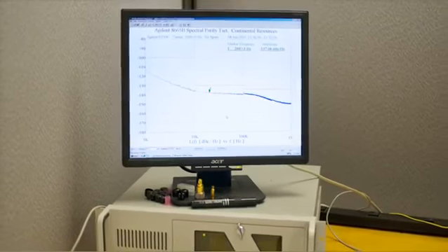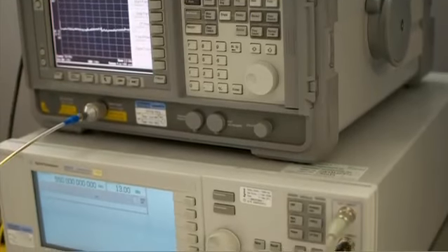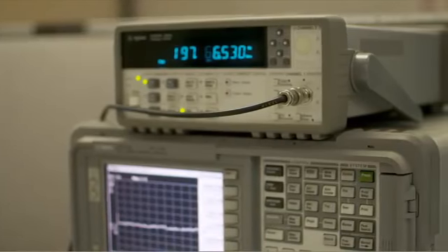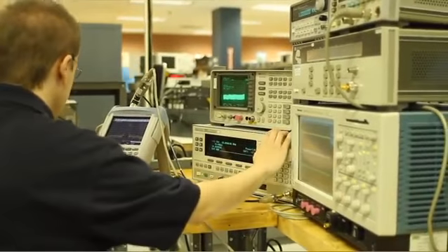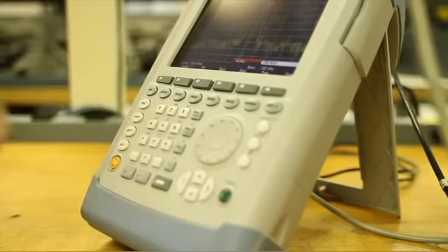Due to the high-speed demands of telecommunications, the purity of the signal is extremely important. So if you have a signal generator and it's being calibrated, you might want to see if a phase noise system is being used on yours. You can rest assured that we do have the phase noise system and it is being used properly to ensure that the specifications of the manufacturer are met, and we are checking all parameters of every piece of gear that leaves the lab. Not all calibrations at all cal labs are equal.